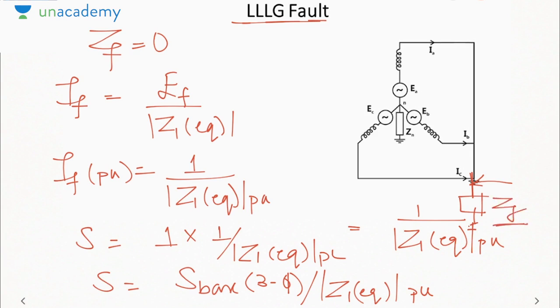Otherwise, you can take ZF equal to 0 for the case of triple LG fault. So these are the two types of symmetrical short circuit fault in which all the 3 phases experience the same short circuit condition, hence the 3 phases will be identical. Hence the system will be balanced. Now, as I told you, 3-phase short circuit fault is the rarest as well as the most severe type of fault. Hence, the circuit breaker rating will be decided on the basis of 3-phase short circuit fault.